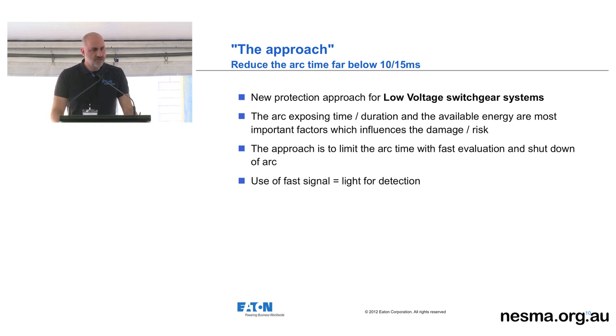So in the arc quenching game, the approach, like any approach when you're talking about arc fault protection, is time: to kill the arc in the quickest possible time. The time that the arc is exposed raises the risk and the danger to the person exponentially. So the approach is to limit the arc time with something that evaluates the arc correctly and kills it in a really timely manner. With arc fault detection systems, they use two evaluating methods. One is light through fibre optics, and the other one is the rising current through CTs. So if only one triggers, it doesn't go off. You don't want accidental mishaps or triggers, so it needs both evaluations to occur for it to say, right, we're ready to shut this down.